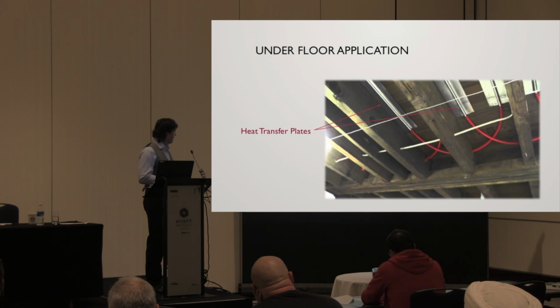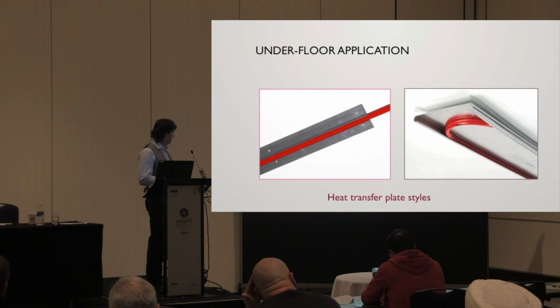So here's your classic underfloor application. There's your heat transfer plates. That's how you pull the pipe in. It can be messy business. What you do is you run along and you pull all this pipe in, you pull the loops all the way to the end, you leave them hanging there, and then you go along and you staple up all of those plates. So if that's 14 and a quarter there, 16-inch center, then you're around 9-inch on center, which is not bad. But you need to have these things in this application. Now, that can be a little bit noisy potentially. You've got to make sure you fasten these things properly. Different ways to do it.